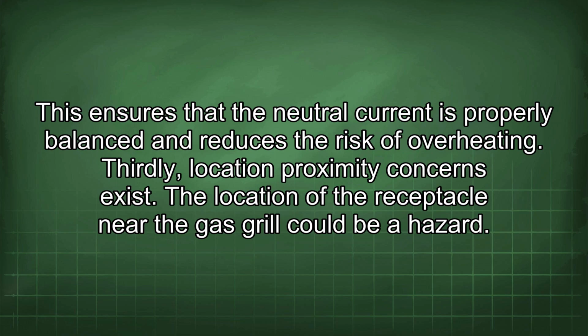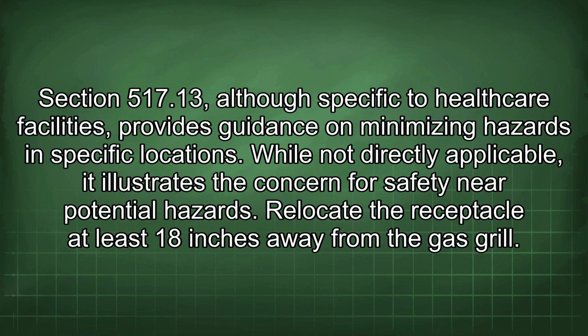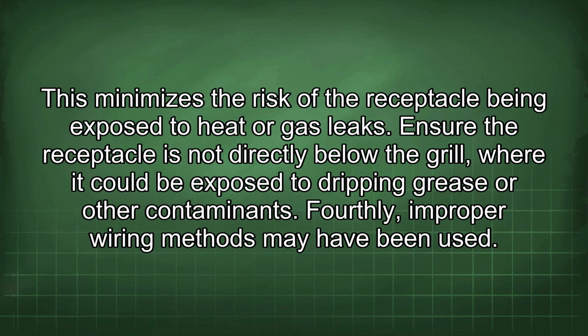Thirdly, location proximity concerns exist. The location of the receptacle near the gas grill could be a hazard. Section 517.13, although specific to healthcare facilities, provides guidance on minimizing hazards in specific locations. While not directly applicable, it illustrates the concern for safety near potential hazards. Relocate the receptacle at least 18 inches away from the gas grill. This minimizes the risk of the receptacle being exposed to heat or gas leaks. Ensure the receptacle is not directly below the grill, where it could be exposed to dripping grease or other contaminants.